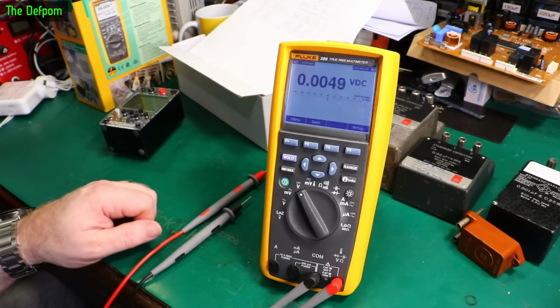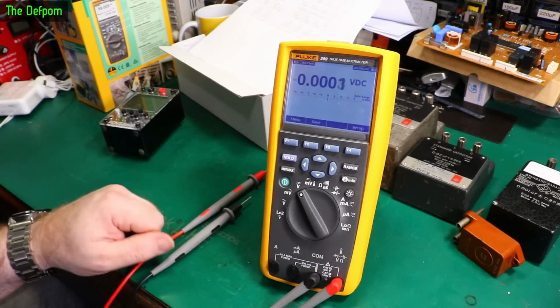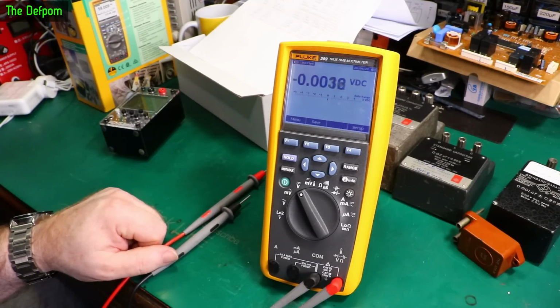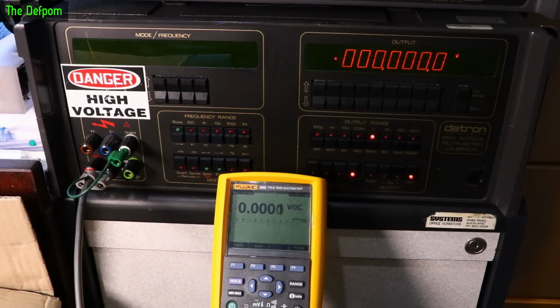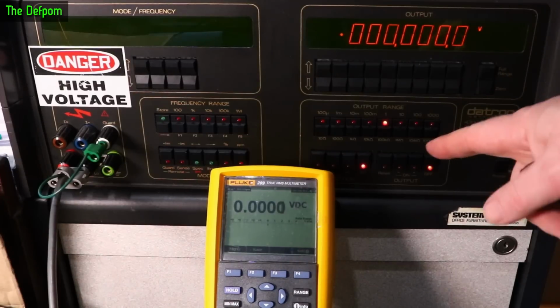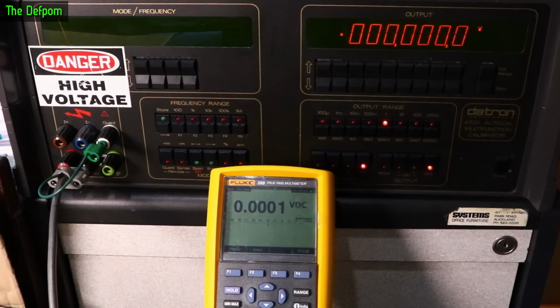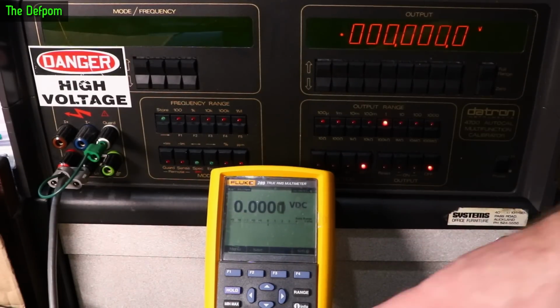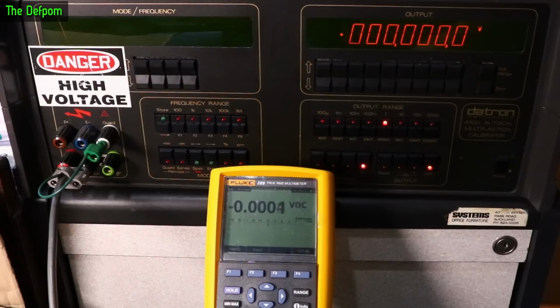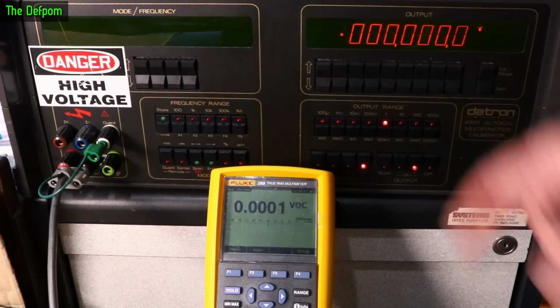So I think the next thing we should do is go to the calibrator and check out these things in a bit more detail. So, to the calibrator. So let's check this thing on the calibrator. I'm going to start with DC volts. I'll do some low voltage stuff first, just to establish some baselines, and then we'll look at the millivolts range, and then we'll do the high voltage stuff, and then we'll do AC volts as well in a similar way, I expect. So set at 1 volt, output on at 0 volts.